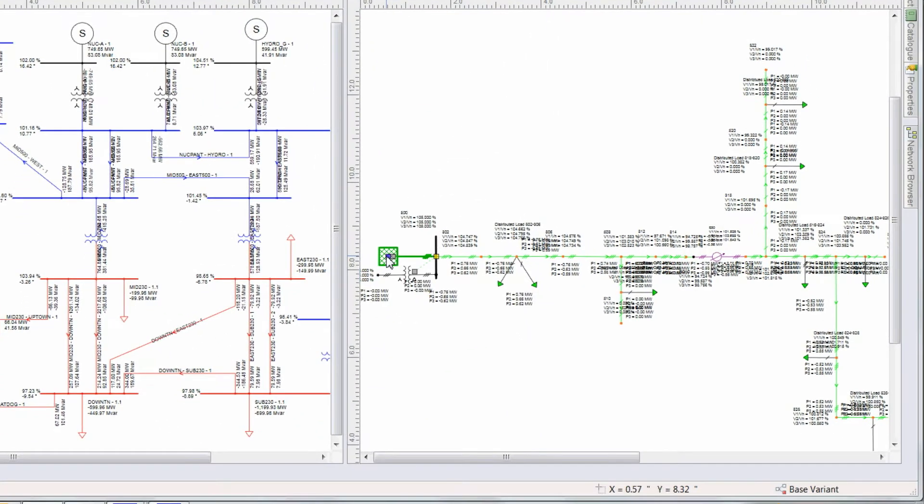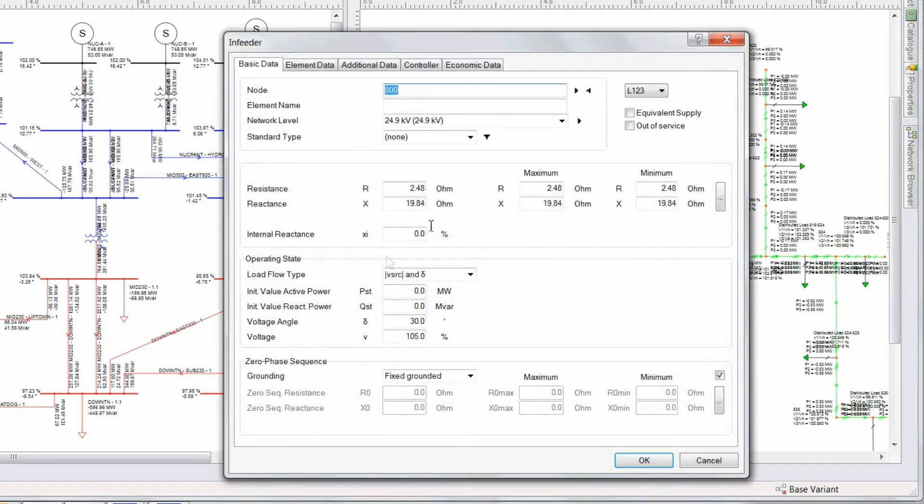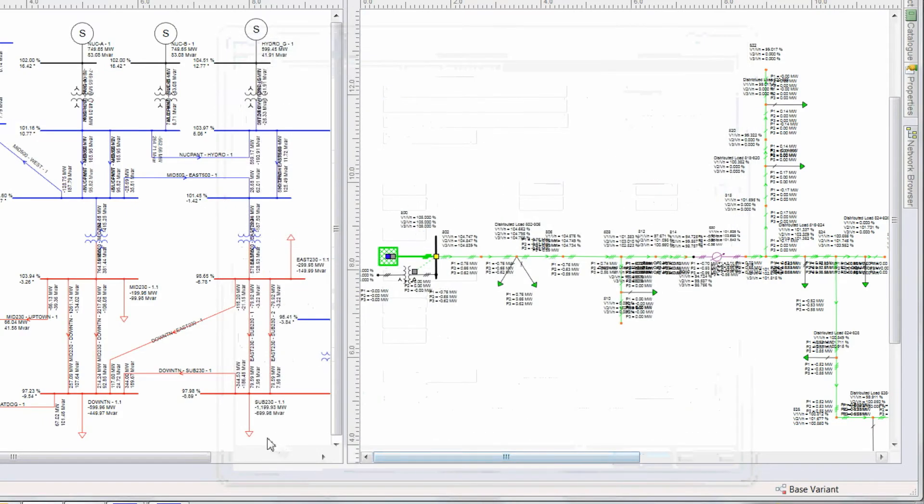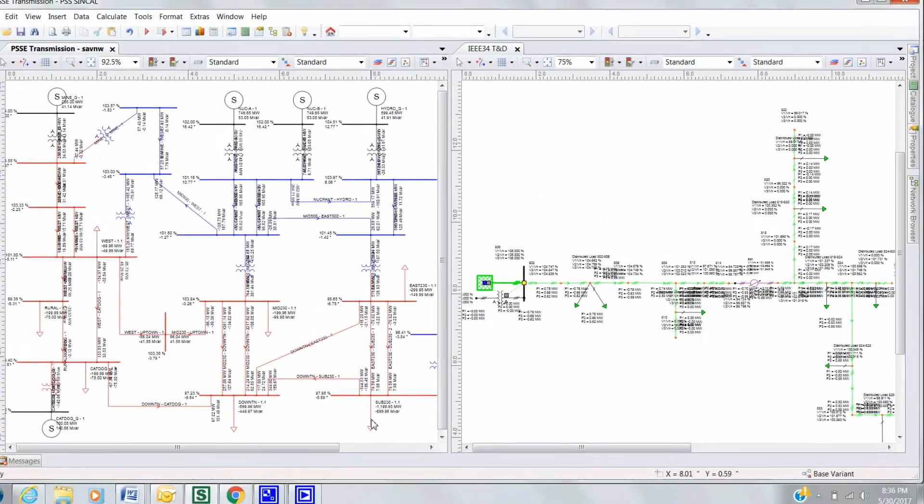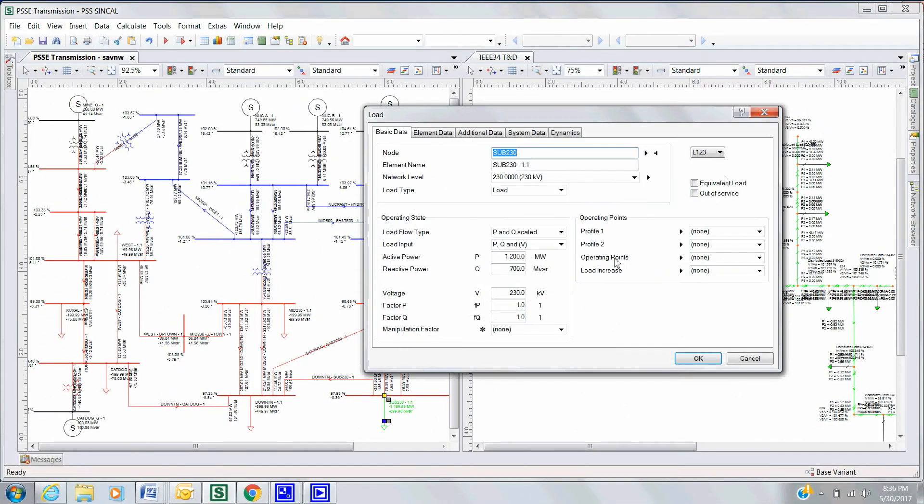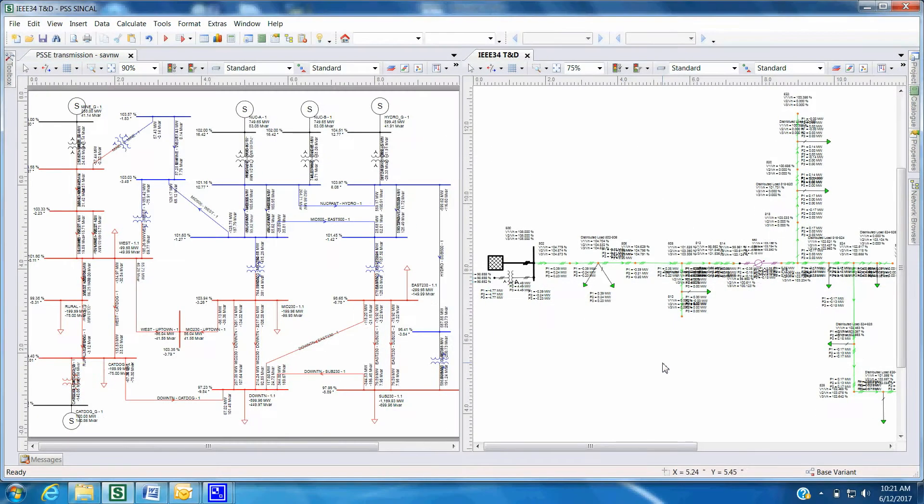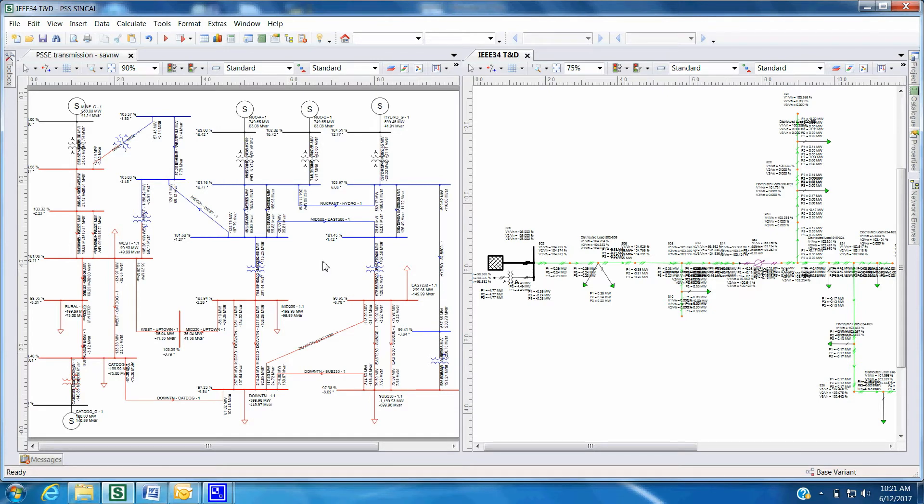Set the load and swing bus to equivalent elements to neglect them, since both networks will be connected. The setting up of connection names and making the loads and generators at the connecting points equivalent can be automated via scripting. We can run analysis from the distribution or transmission side. In this demo, we will show how to analyze an integrated T&D study from the distribution side.